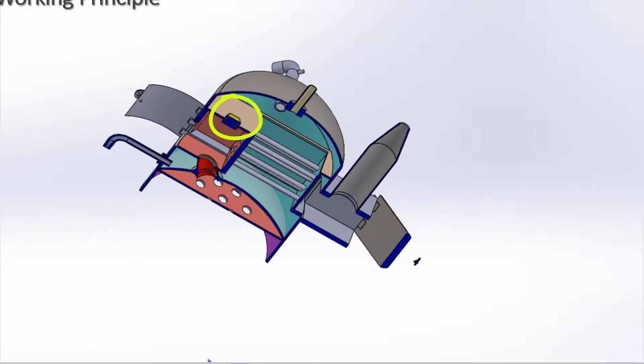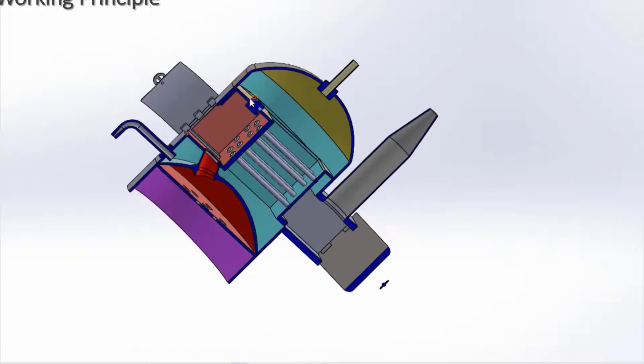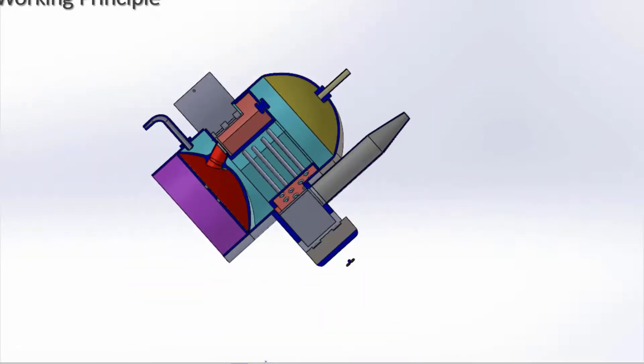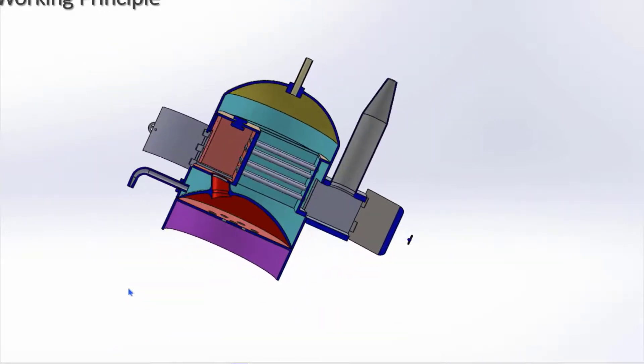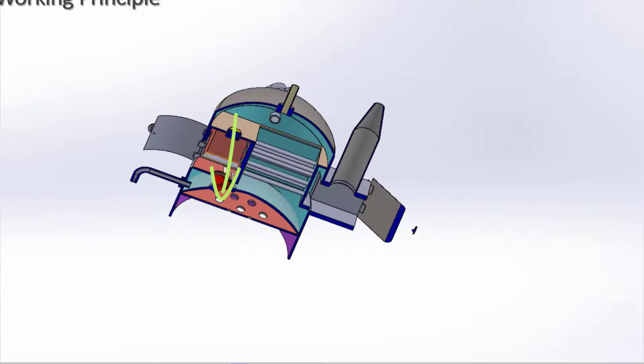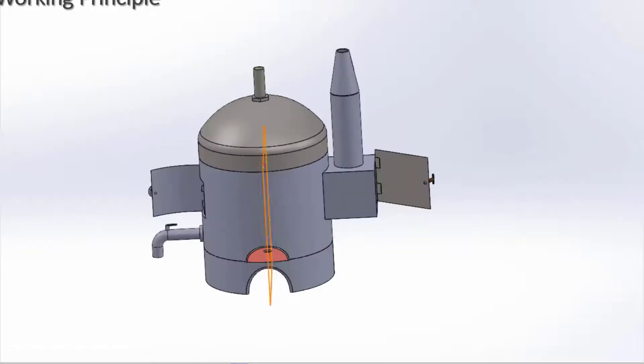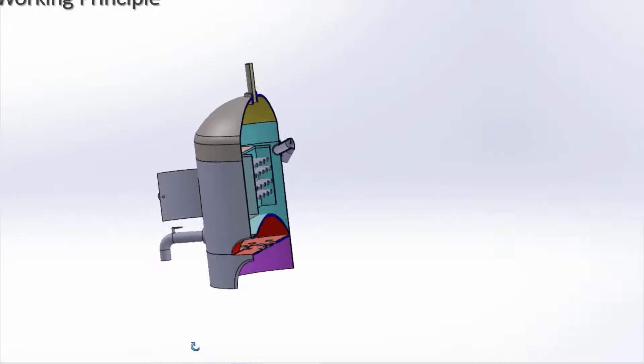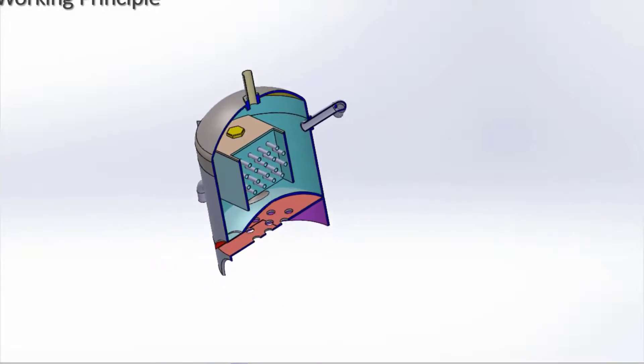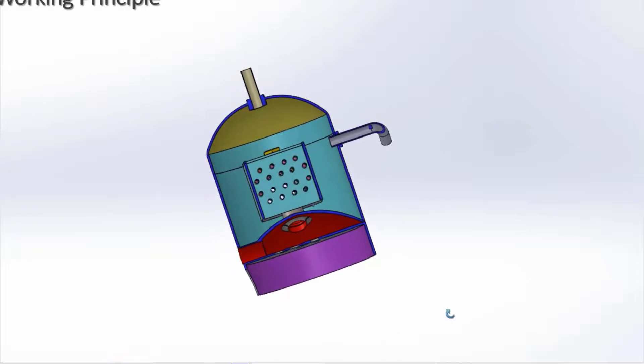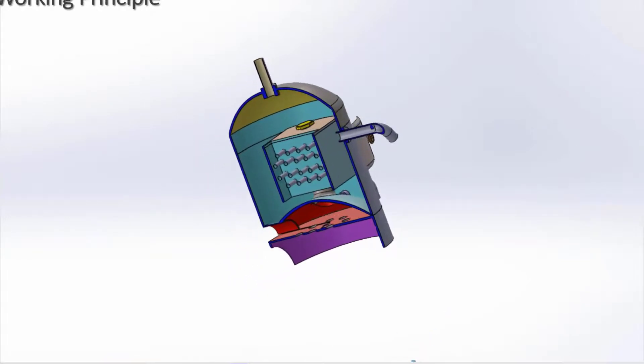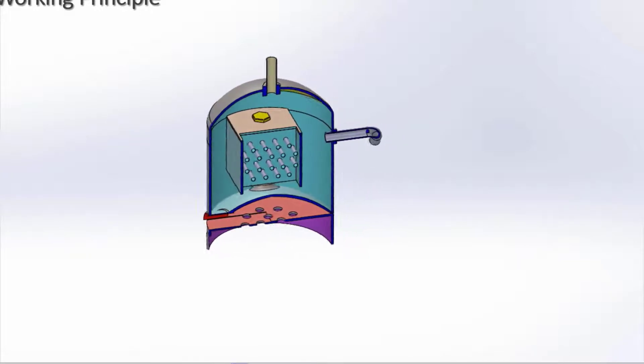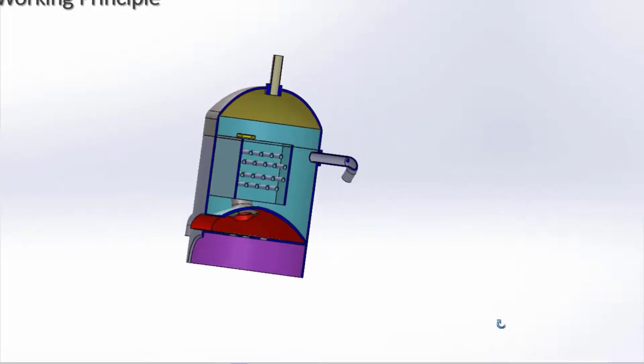This is the fusible plug. If the water level goes down, the plug is melted and water enters through this hole to the furnace to stop the fire. Now you can see the cut section at the vertical side plane. Look at the multiple fire tubes surrounded by water. Water receives heat from the top of the furnace and also from the fire tubes.